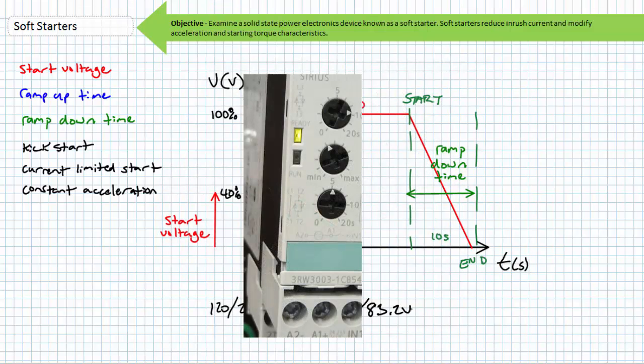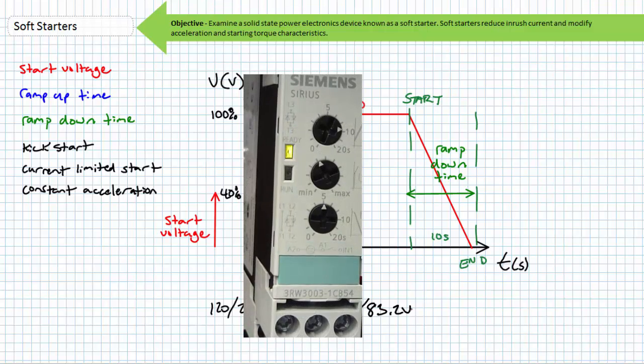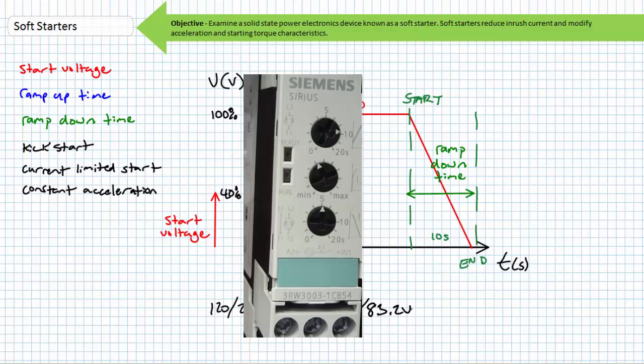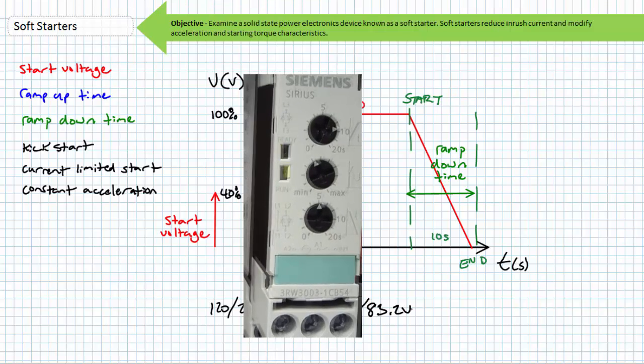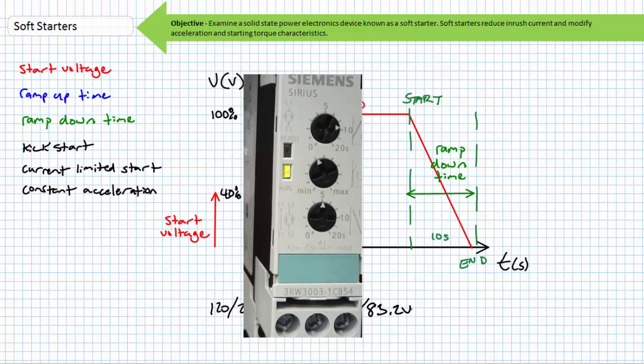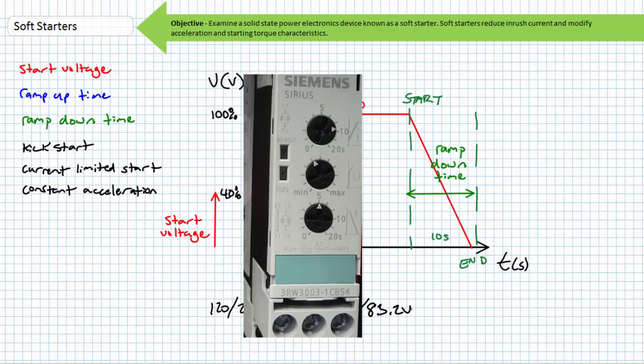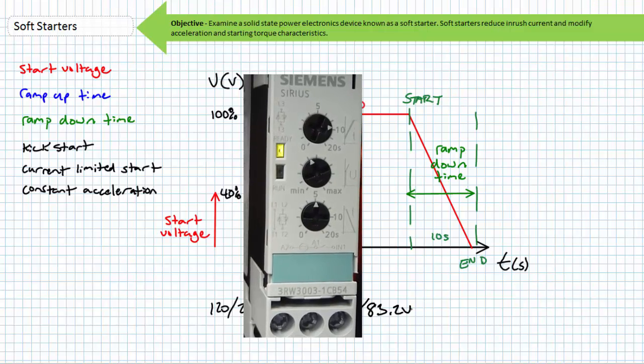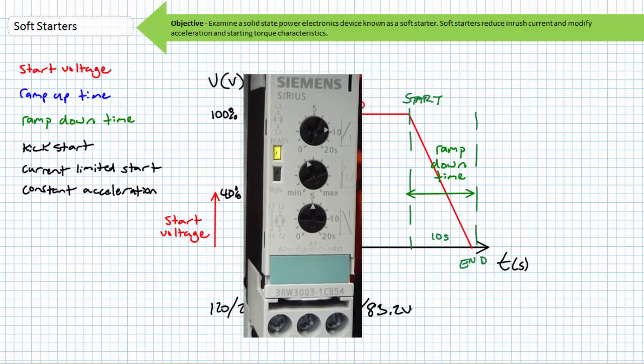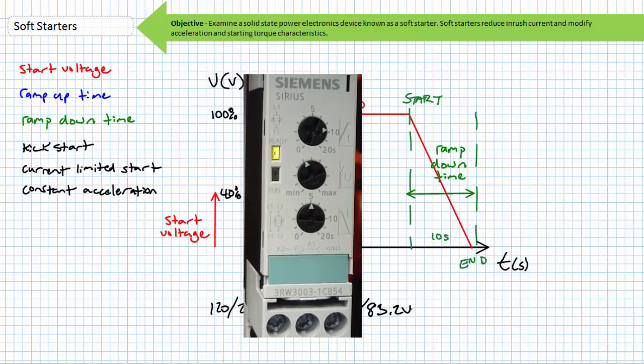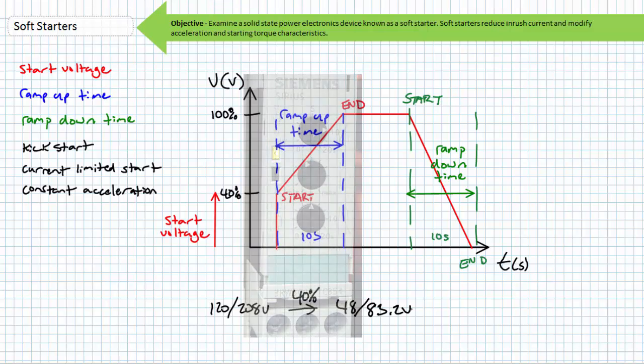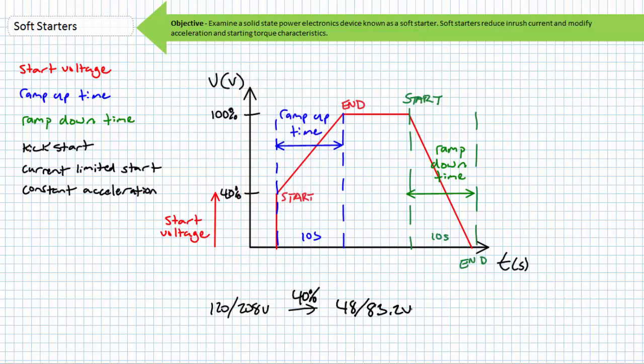The ready light remains illuminated when the device is powered up and ready for action. The ready light blinks upon being enabled and continues to blink during the ramp-up period. The ready light turns off and the run light comes on when full voltage is applied. Finally, during the ramp down time, the run light turns off and the ready light blinks until 0 volts. The ready light remains illuminated and the soft starter is ready to initiate another ramp-up event when enabled. These indicator LEDs are often invaluable troubleshooting resources.